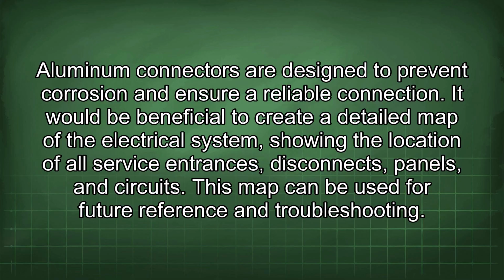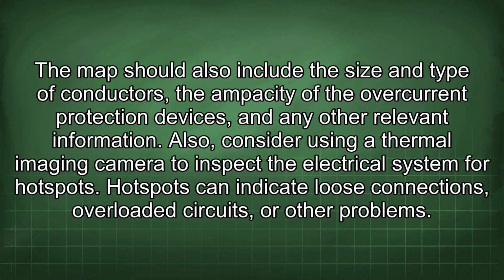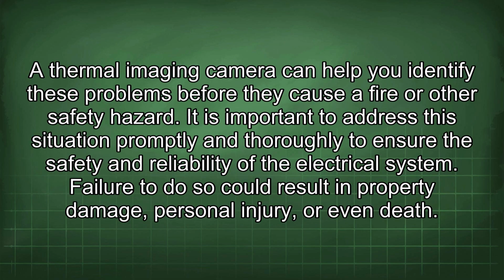It would be beneficial to create a detailed map of the electrical system, showing the location of all service entrances, disconnects, panels, and circuits. This map can be used for future reference and troubleshooting. The map should also include the size and type of conductors, the ampacity of the overcurrent protection devices, and any other relevant information. Also, consider using a thermal imaging camera to inspect the electrical system for hotspots. Hotspots can indicate loose connections, overloaded circuits, or other problems. A thermal imaging camera can help you identify these problems before they cause a fire or other safety hazard.